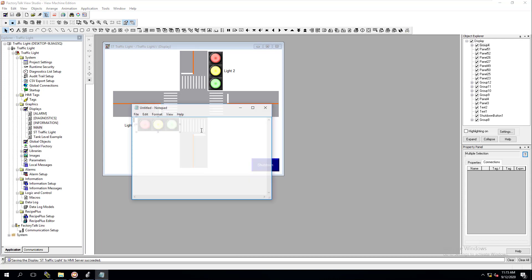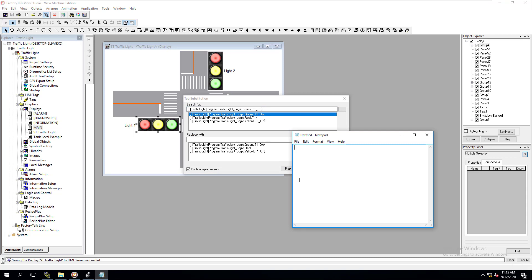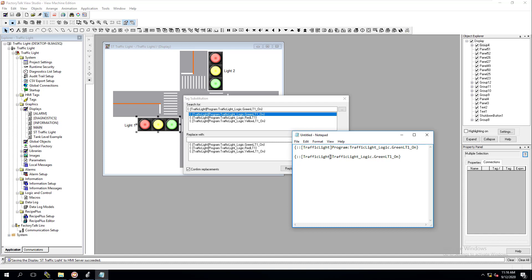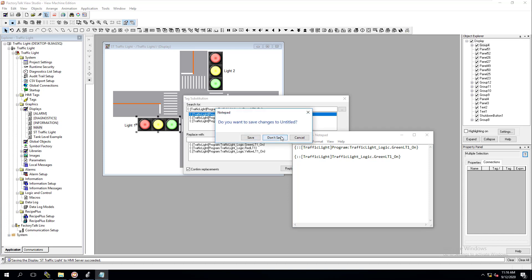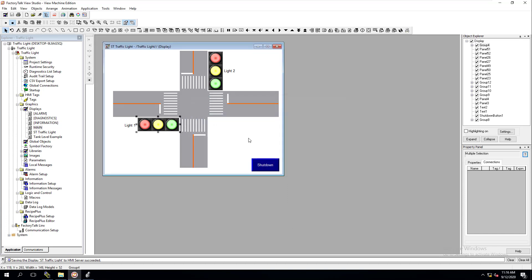What I do often — and here's a little tip — is I'll go into a Notepad, then come in here and drag this over and edit it over there. I'll duplicate that and say, my new tag — oh, it's no longer a program scope, it's just a shortcut here and then the program tag here. Say for instance I took all the tag structure for the structured text and took it out of program scope and made it controller scope — I could easily come in here and change that just by tag substituting it, but I like to write it out in Notepad so I understand where I'm changing it. That's one little tip to help you if you get into large systems. For what we just did here — really simple, real cut and dry, and just another way to save you time and effort.